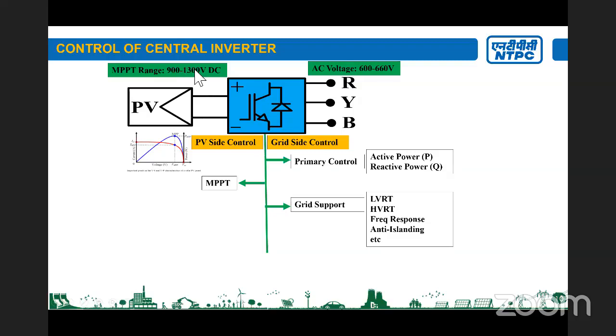The advantage they are getting is that they are able to increase the AC voltage. By doing that, with the same converter, they are able to increase the converter capacity. Say if the converter with 900 volt comes with 2.5 megawatt, and they increase the voltage, then the capacity of the same converter will increase without much addition of any component. It will increase by say 10 to 15%. So they are now doing all these things.